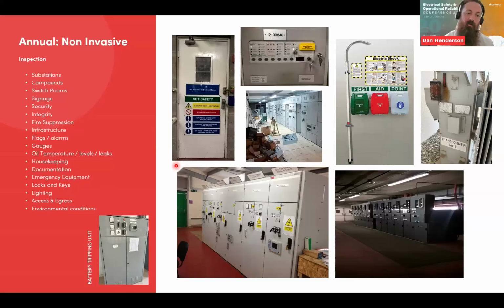My most important point is probably your battery tripping units. The amount of times I go to site and they'll either be turned off, or I've had them where I'll knock the supply off just to do a check and there'll be no voltage in the batteries. They're just massively overlooked in a lot of places in terms of maintenance. And it's the most important bit of equipment in that substation. Without those tripping batteries, none of your protection is going to work. So you've got no protection on your board at all. And it's something that's just massively overlooked.